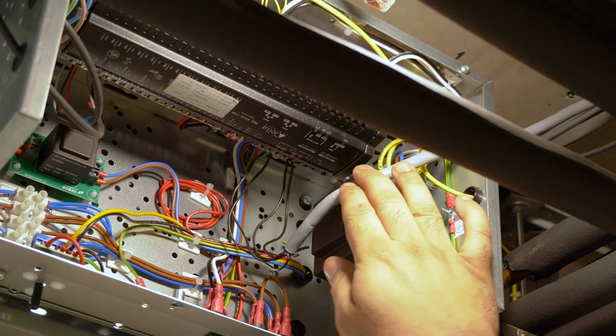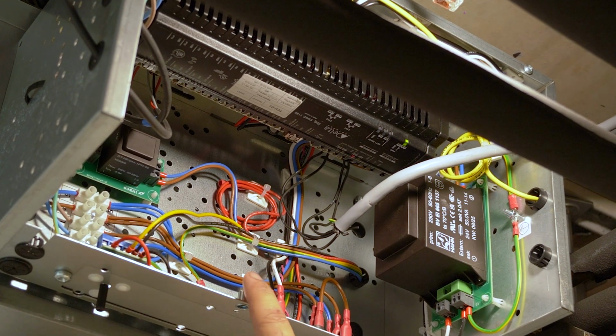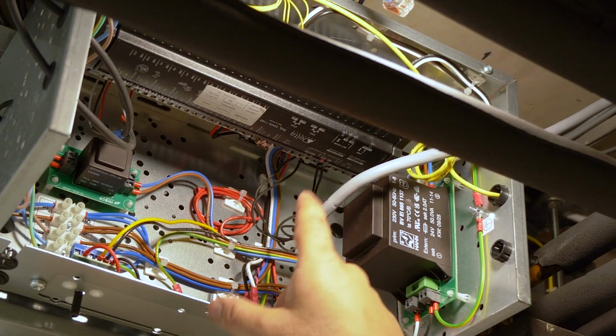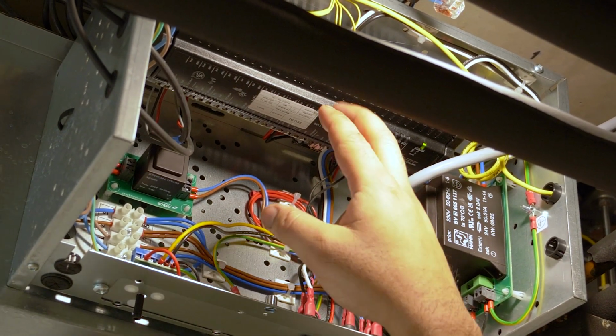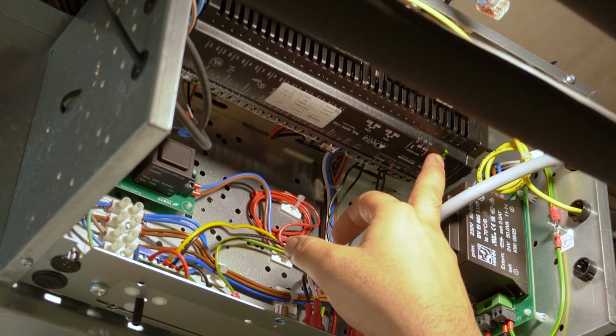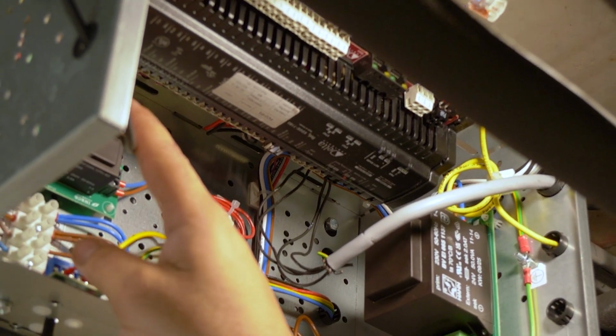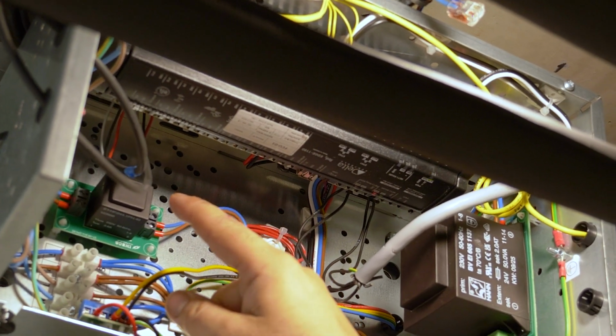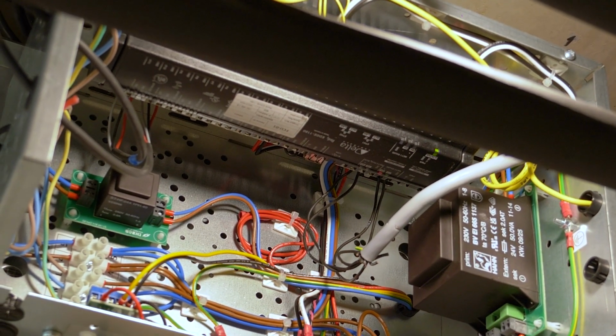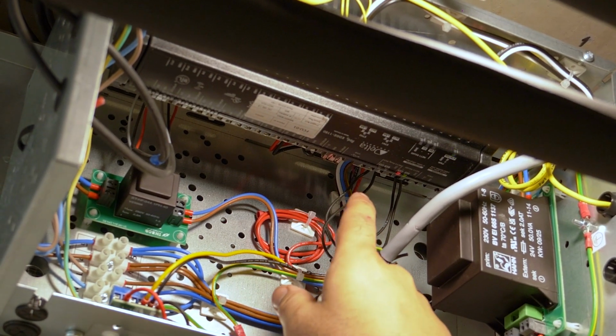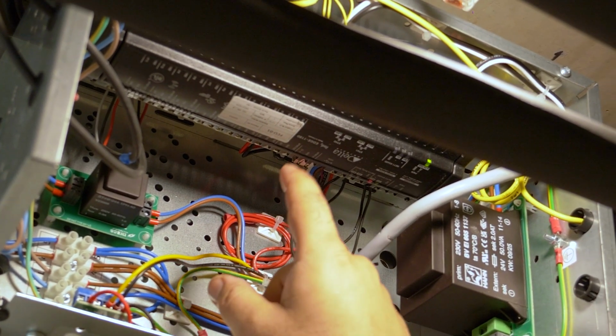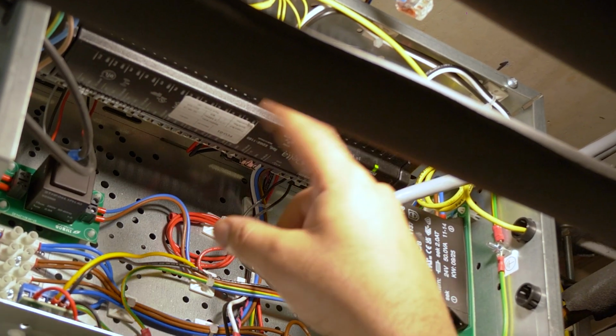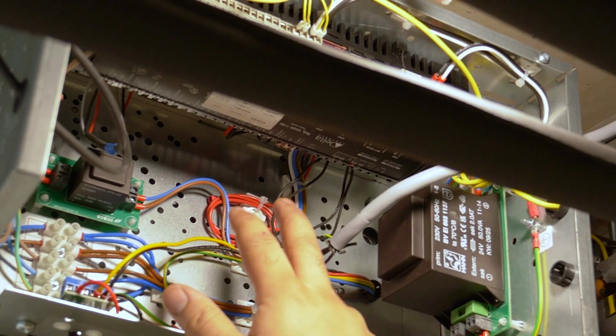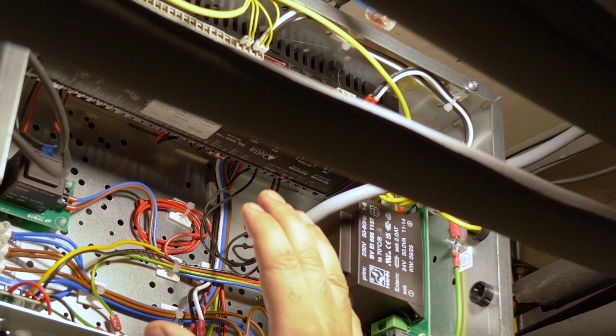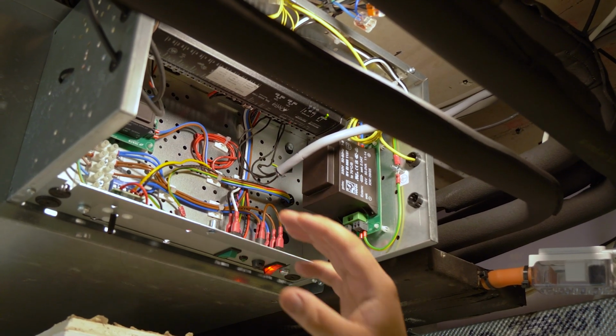So we're looking at the Delta fan coil unit controller. Fan coil unit controller is a 230 volt supply, comes into the transformer, and a section of it is stepped down into 24 volts DC. So we have power supplies coming into the controller. You'll see the controller has a status comms symbol there. We have our cooling and heating valves set up on the output configurations here. We have fan speed set up mechanically from a potentiometer here, and then the unit will adjust this according to the return thermostat and the actuator positioning. We have thermistors here, supply and return configured, and then we have our thermostat delta connection here. This side of the fan coil unit is very key. We configure this when we set up new fan coil units on site according to the type of interface or what we're doing.